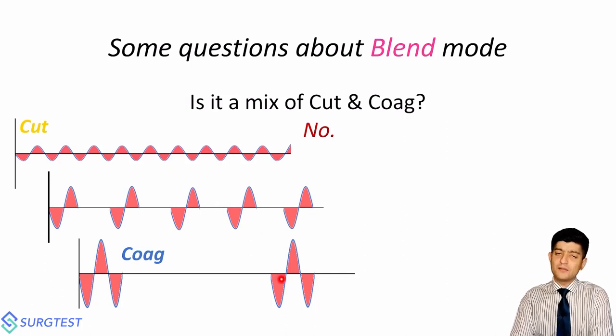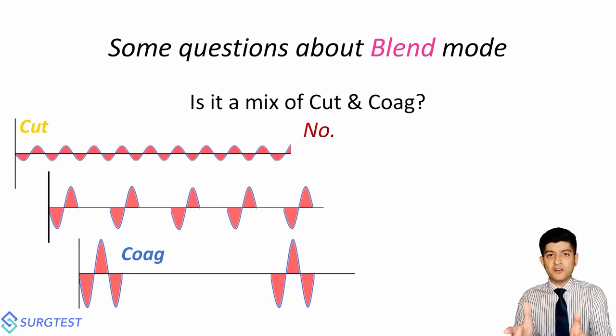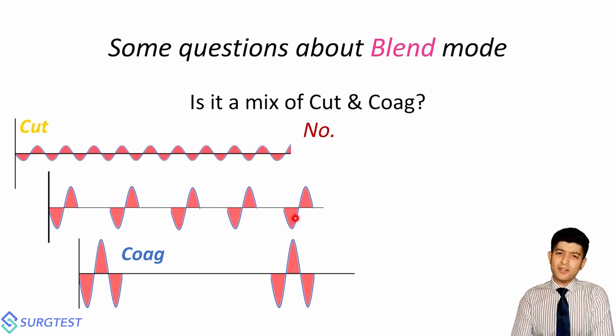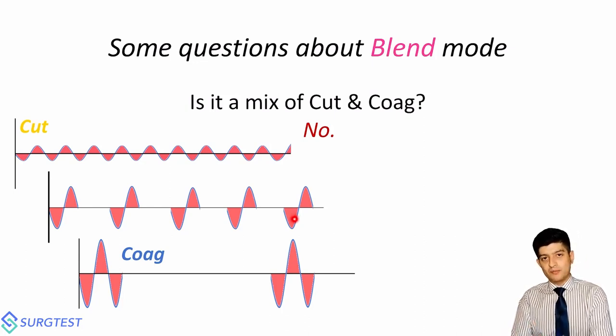So the blend mode is somewhere in the middle of all of this, but it does not give you the best of both worlds. For example, I showed you guys that surgical video of me going through the tissues with a cutting current. Tissues get vaporized very easily. Yeah, that's a feature of the cut current. Coagulating current is extremely good for coagulating raw areas, like say a liver bed or when you don't have very distinct bleeders. Does the blend mode adequately achieve both of those? Not really. So it doesn't serve both functions. I would rather say you identify the problem in your surgical field properly and use either cut or coag depending upon what the solution calls for.